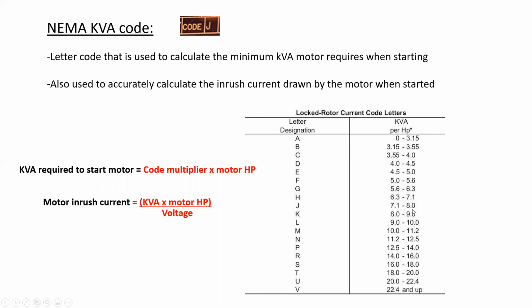This is by no means a standard rule, but for our purposes, we always choose the upper end of the range provided. Now, if we wanted to calculate the motor inrush current, because when a motor starts it will draw more current than what the nameplate states, we can use this quick calculation in order to validate it. Remember, if it's three-phase, you've got to have that three-phase root 3 in there as well.